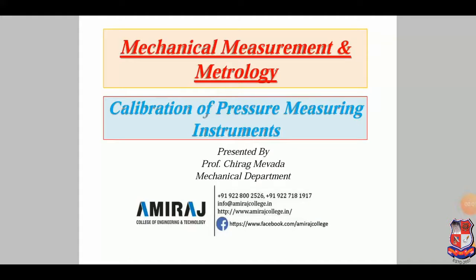Hello and welcome everyone. In this lecture, I will discuss calibration of pressure measuring instruments. Basically, calibration is the process of adjusting the instrument output signal as per the known input. So with a change in input, the output should change in proportion. The basic calibration procedure includes zero, span and linearity adjustment.